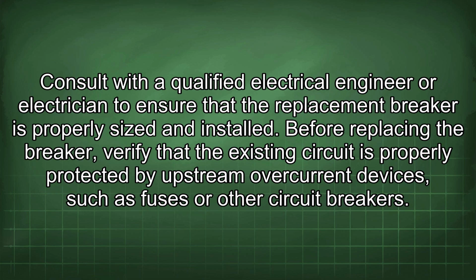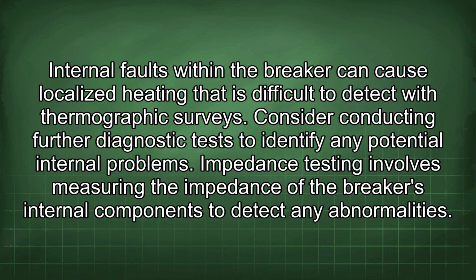Before replacing the breaker, verify that the existing circuit is properly protected by upstream overcurrent devices such as fuses or other circuit breakers. Internal faults within the breaker can cause localized heating that is difficult to detect with thermographic surveys. Consider conducting further diagnostic tests to identify any potential internal problems.